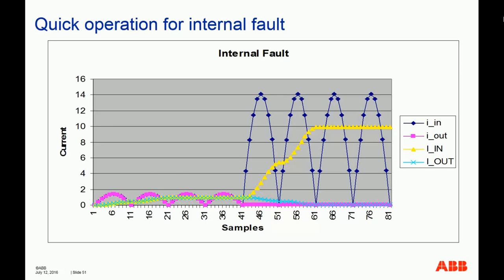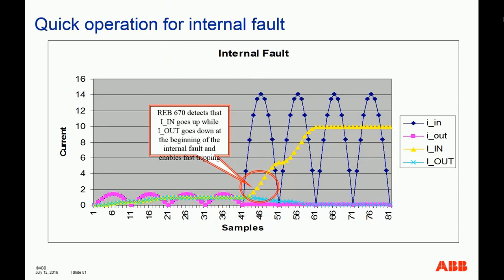So this is an internal fault. During an internal fault, all the currents go in the same direction. So really, all the currents are incoming current, let's call it that way. Your incoming current rises and your outgoing current drops. The yellow and the light blue depict the fundamental 60 Hz phasor RMS values, for example, and the phasor values are what the relay operates on. You can see that as soon as the differential current goes above the operation level, a trip is issued. This is how the relay operates during an internal fault.